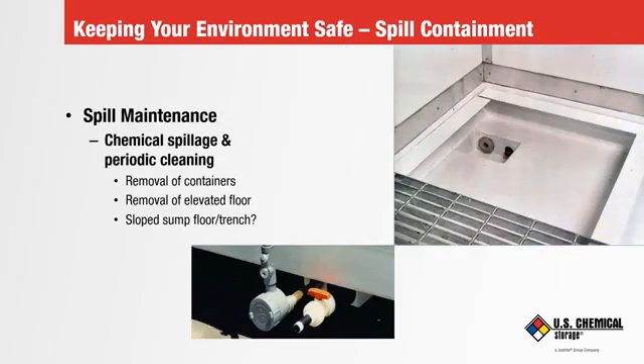Other factors must be considered that determine sump floor height. If there is a water-based fire suppression system, the capacity of the sump height must add in the total amount of dispensed water in a 20 or 30-minute deluge. This is dependent on local codes and/or opinions of the local authorities having jurisdiction.